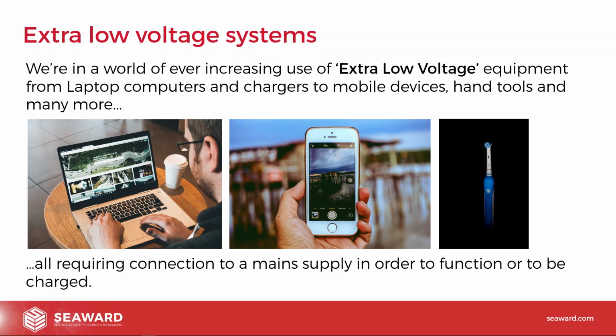And it's quite a misconception a lot of times that people just say, yeah, well, it doesn't need doing, and you'll see videos where somebody's put a PAT testing sticker on a laptop and they get ridiculed, saying, oh look, just money grabbing, testing things that don't need testing. But actually as a duty holder, we have a legal duty to make sure these things are safe. They are systems, they do fall under the Electricity at Work Regulations 1989. And we might not be worried about getting electrocuted by these things, but there's a hell of a lot of chargers that are catching fire. There are substandard chargers, and you get batteries in phones and laptops catching fire, and all these sorts of things.